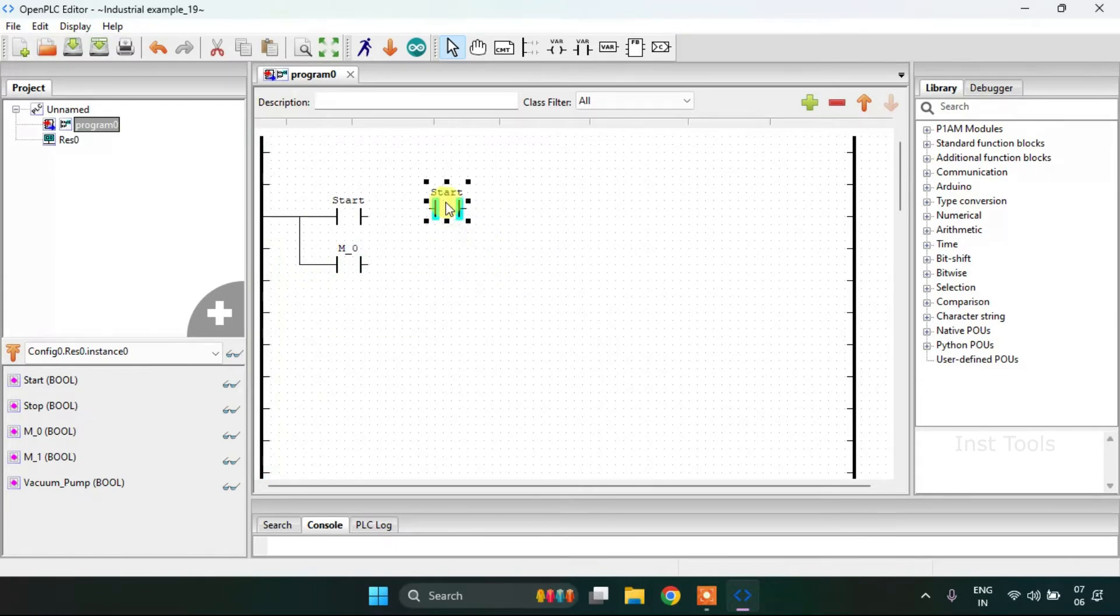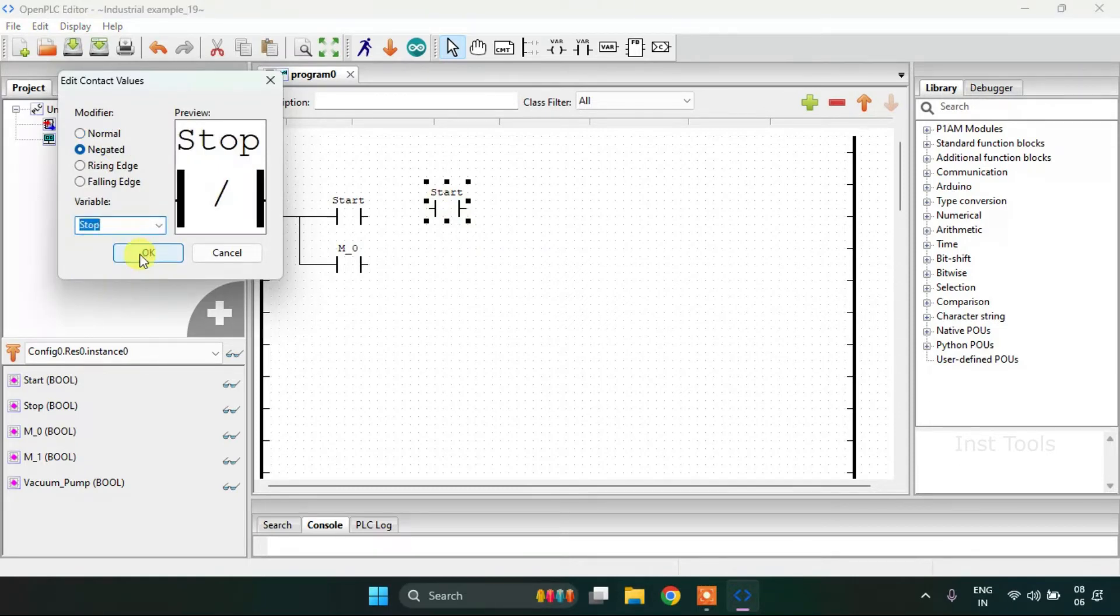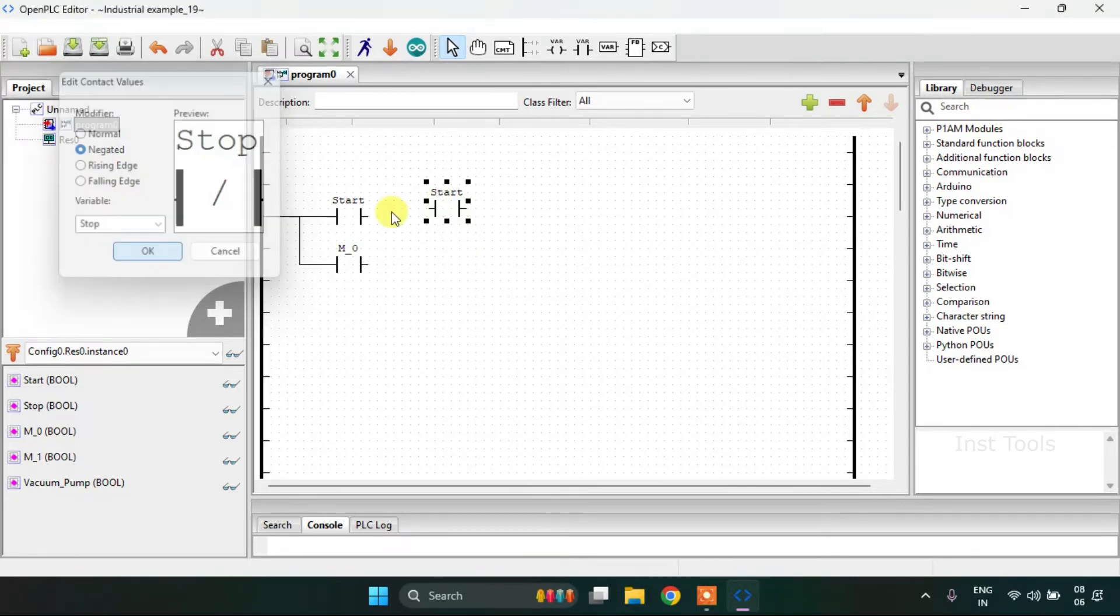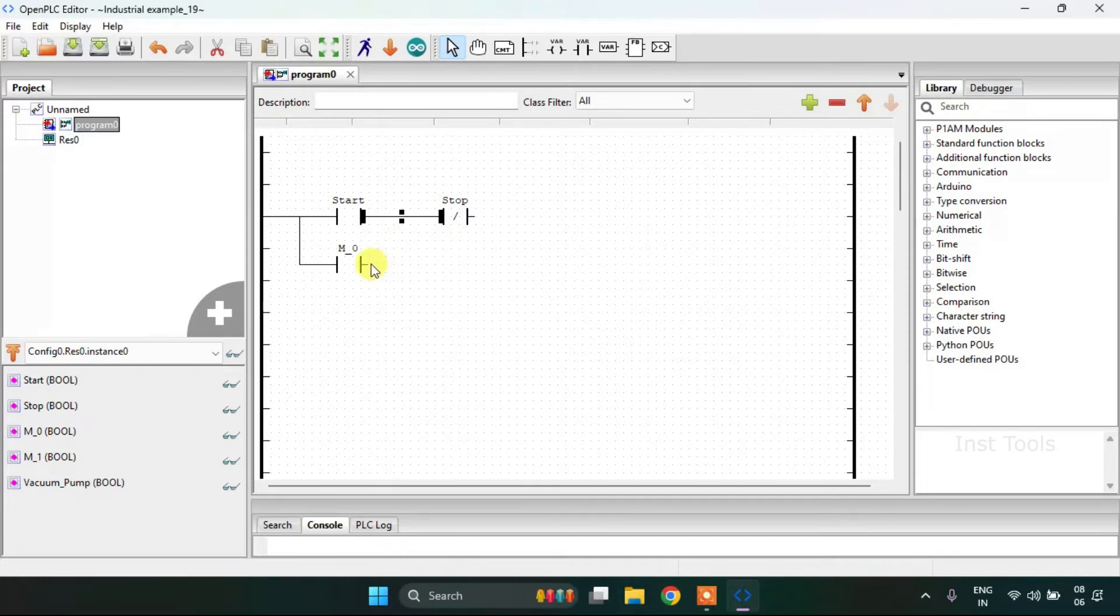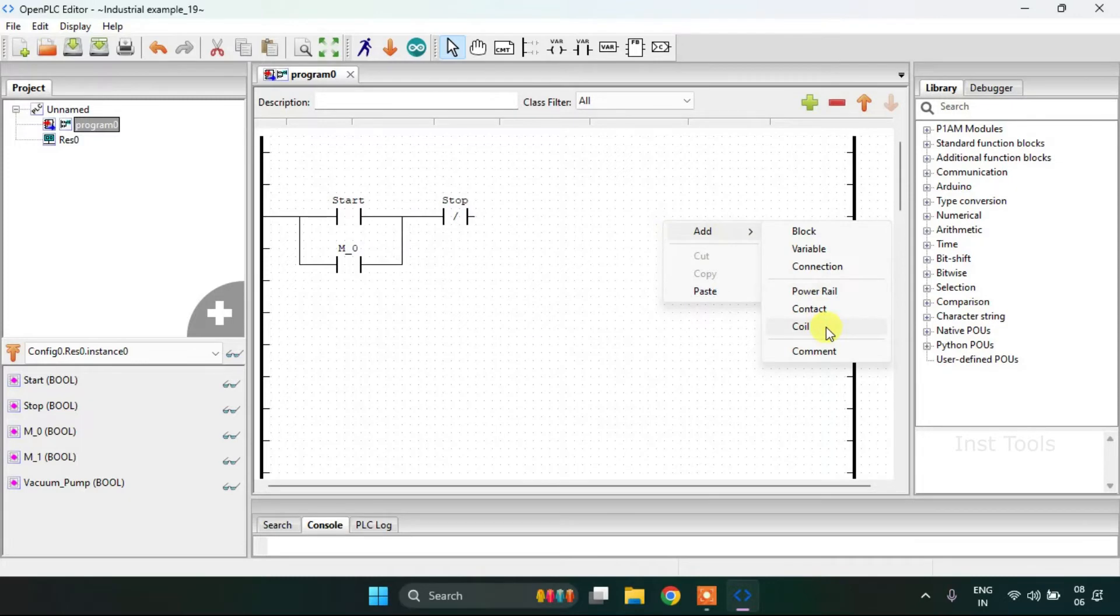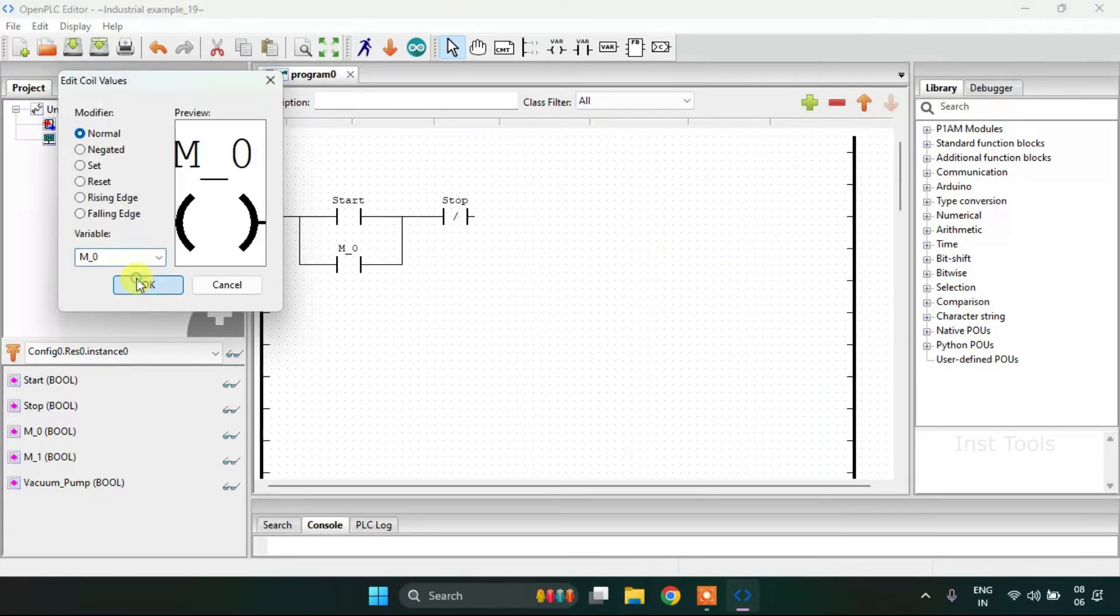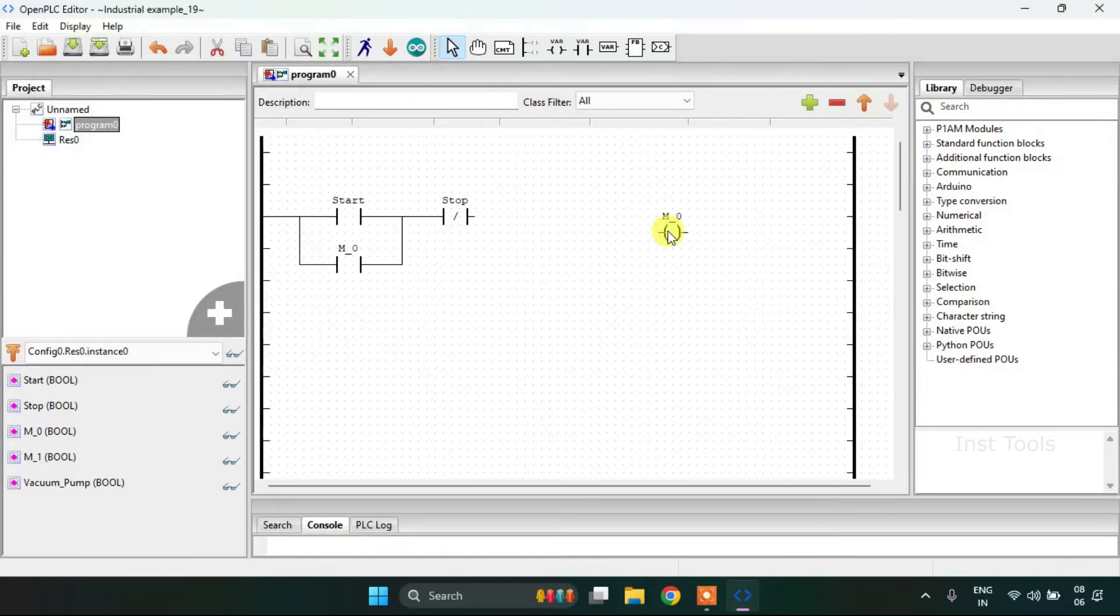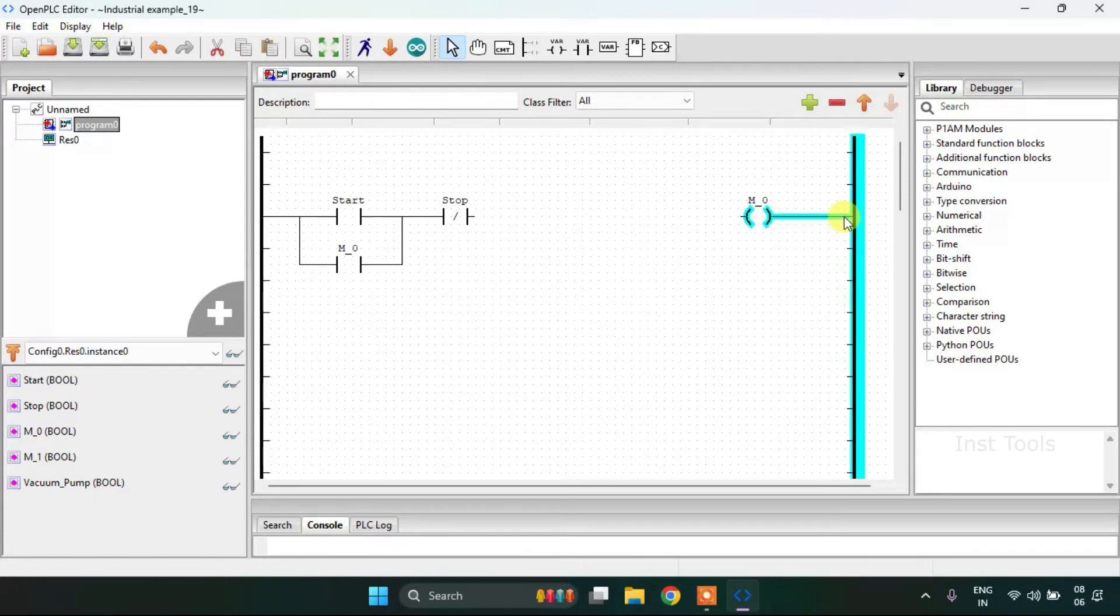I will paste another contact and modify it to negated and address to the stop. Then I'm going to keep it in series with the start. And for the coil, I will address it as memory bit 0. I will adjust the size and join these pins.